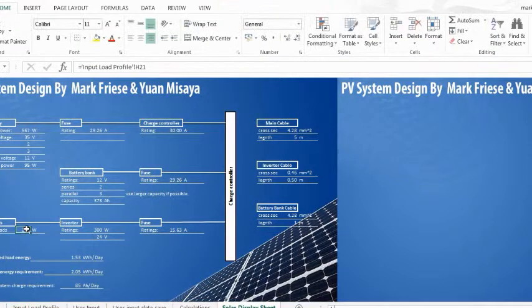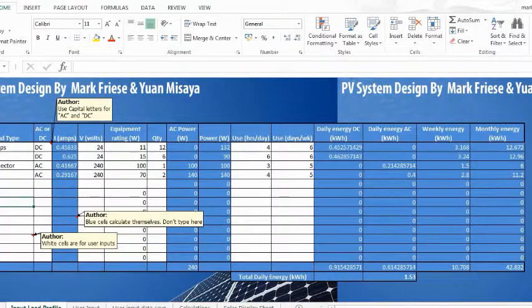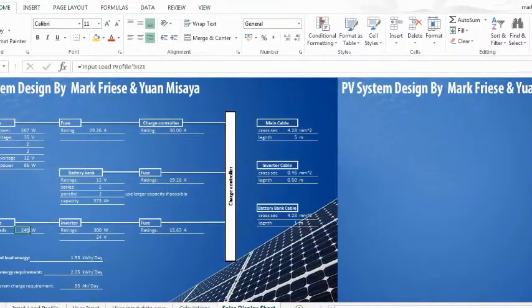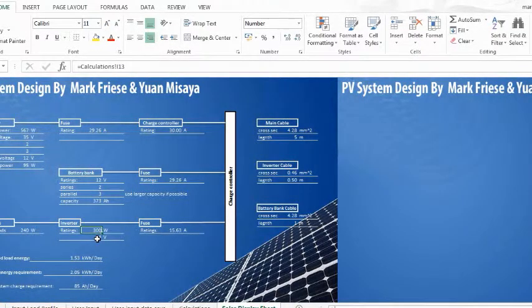So next we have our AC loads, which were 240 watts. So that's what this wee column was for here. So back to our display sheet, which means when you just use a round up, you're going to get an inverter probably of around 300 watts, and that should do you for the maximum AC demand that you've got there.